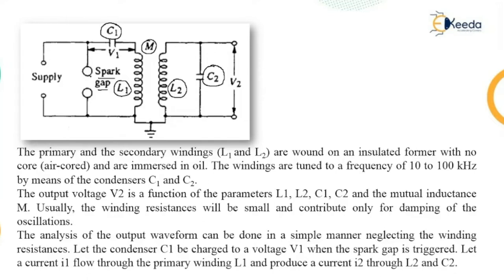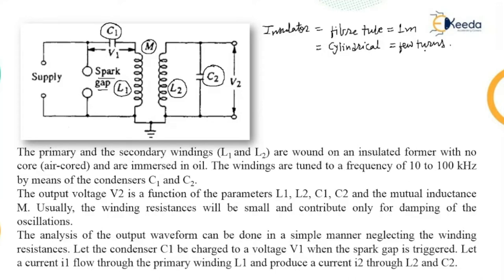The primary coil is wound on an insulator — a fiber tube material of approximately one meter in length — representing cylindrical or helical winding. It consists of a few tens of turns of copper strip or tubing. The secondary winding is spaced quite away from the primary winding on another concentric fiber tube of the same kind, with a few thousand turns.